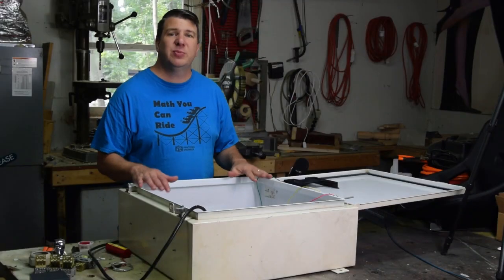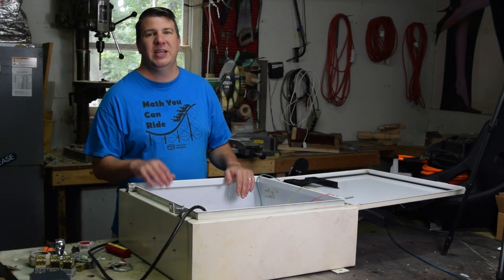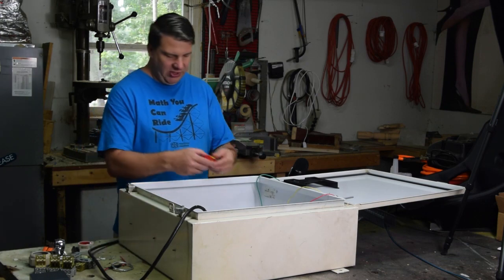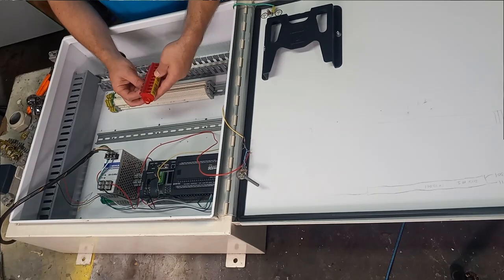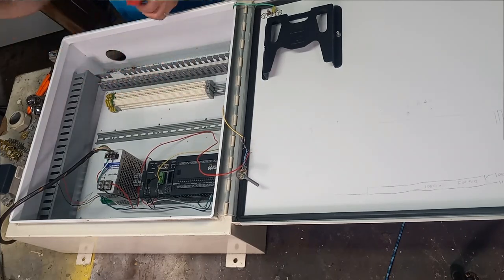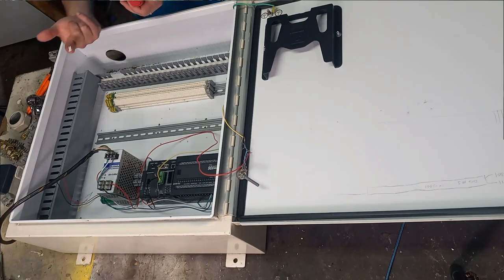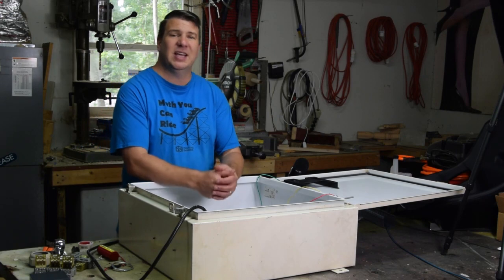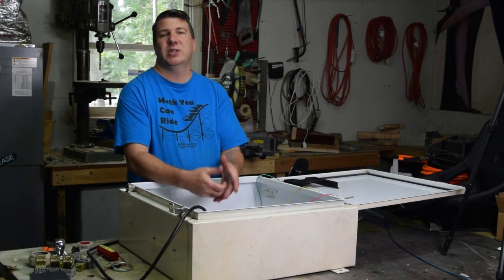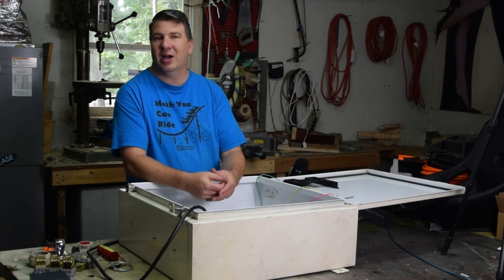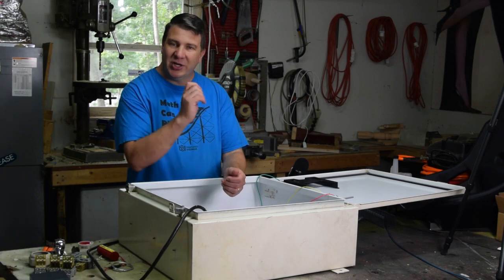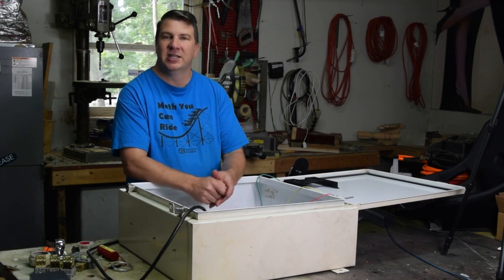Number seven. In this box, all of your wires must be labeled. Yes, every one, both ends. I used to use these peel and stick labels right here. They're just not good. They're cheap. You've already got some of the stick off of it and on your hand, then you got to pull it again and you get to wrap around. So it's lost a lot of stick before you even get started. What I recommend instead is getting a label maker, and most label makers have heat shrink tubing options that you can print a wire number right on there, slide it in the wire, heat shrink it on, and it looks fantastic. So go that route.